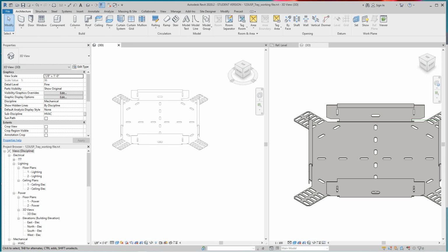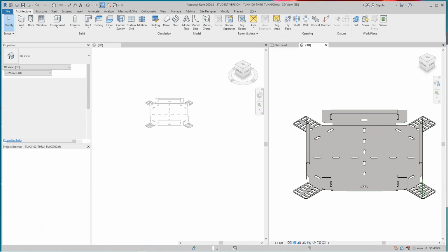Now I can see a lot of red flags here: no connectors, and it's in the wrong category because it's grayed out. Normally what they're going to use in a cable tray project file is going to be a systems template or electrical template. I can't even touch that, see? So we got to do some work over here. So I'm going to just undo this.